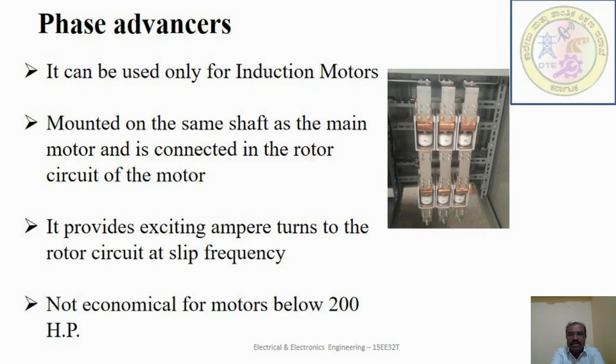The low power factor of an induction motor is due to the fact that its stator winding draws exciting current which lags behind the supply voltage by 90 degrees. If the exciting ampere can be provided from another AC source, then the stator winding will be relieved of exciting current and the power factor of the motor can be improved.